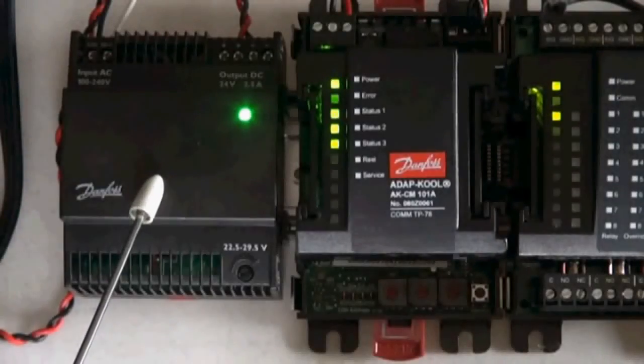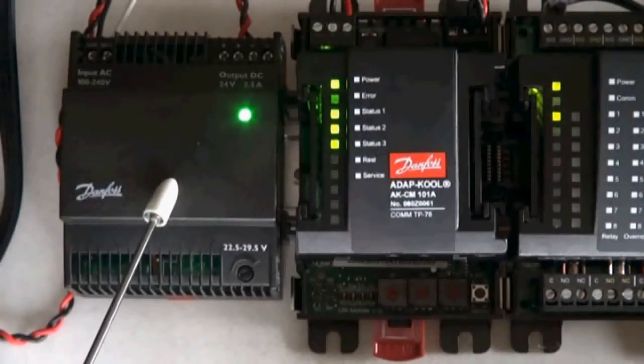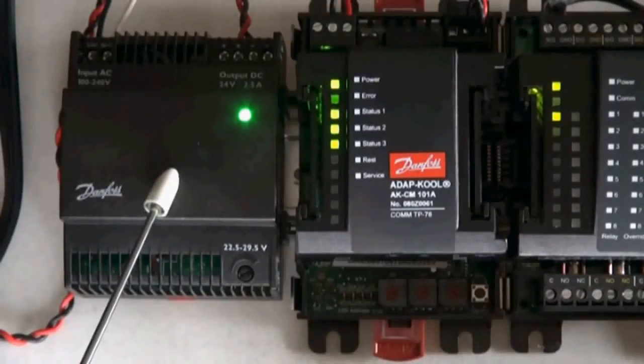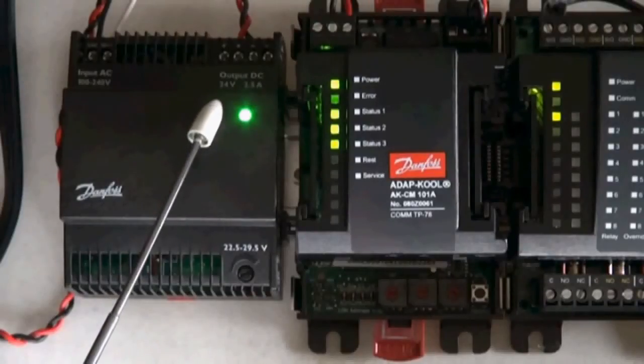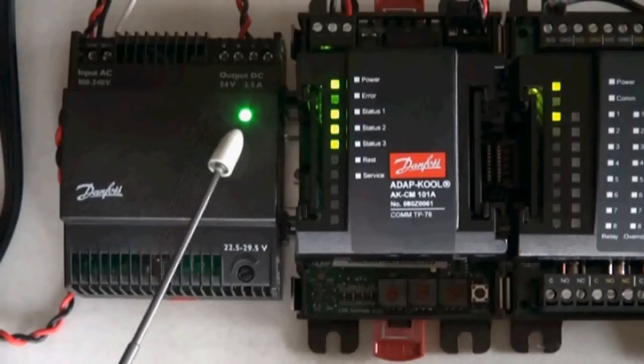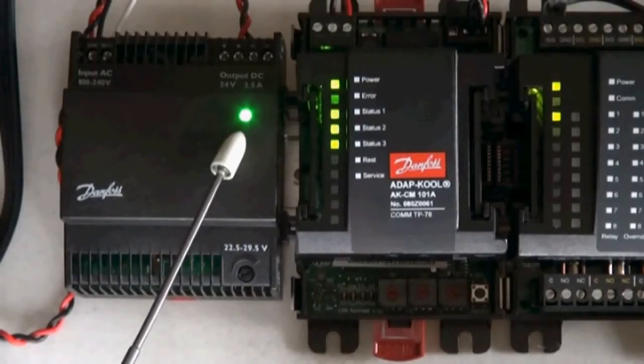This 24 volt DC power supply can be powered with AC voltage from 100 to 240 volts. It provides 2 24 volt DC outputs. This green indicator light means we have power coming to the power supply and the output is not shorted. If the output would be shorted, this green light will go out until the short is removed.